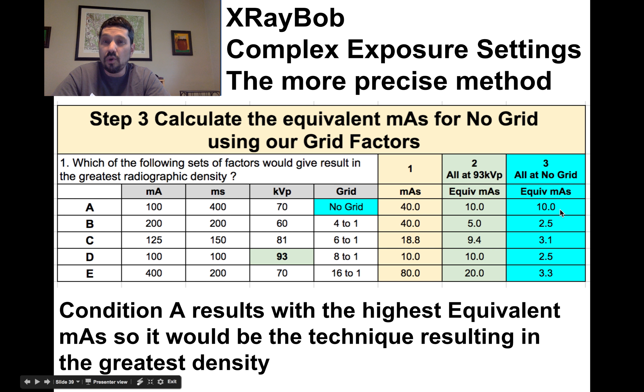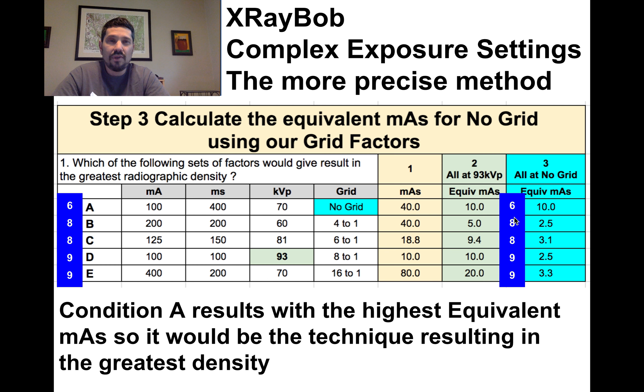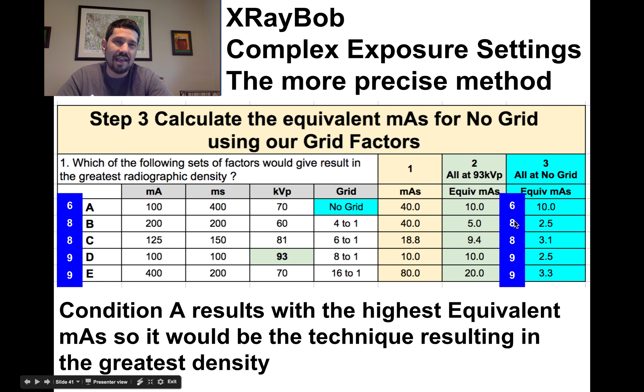If the question asked for the highest or lowest patient dose, we would not use the 15% rule — we'd use the ratio of kVp squared — but that's even more complicated.